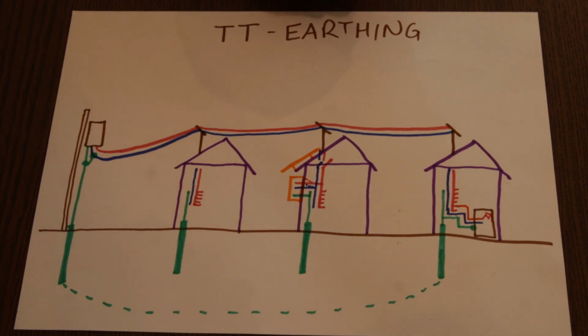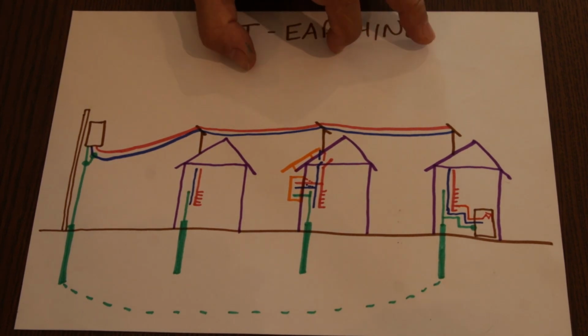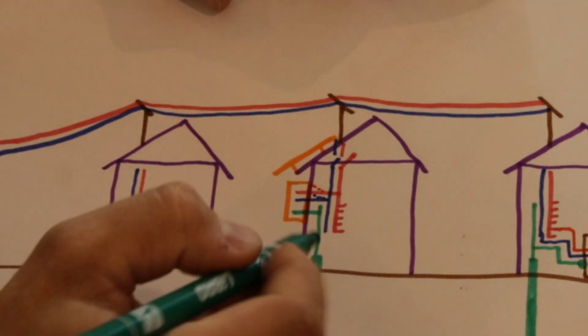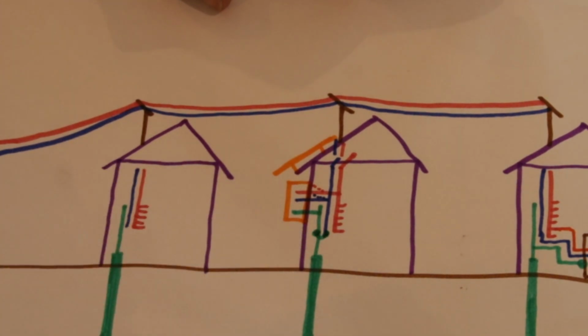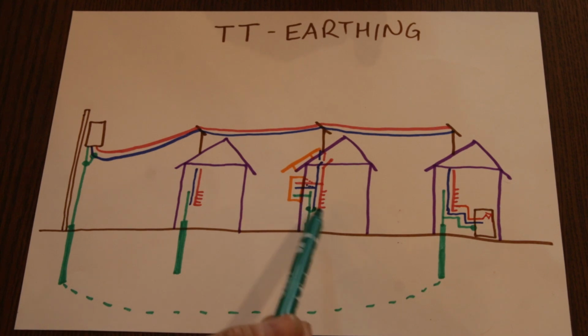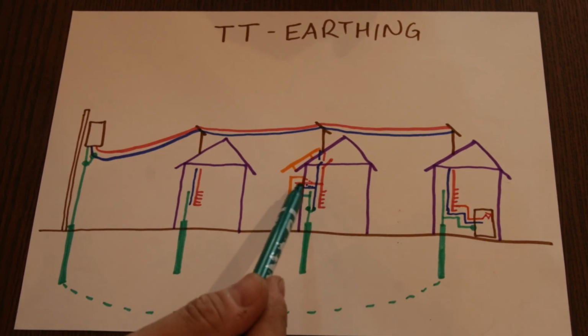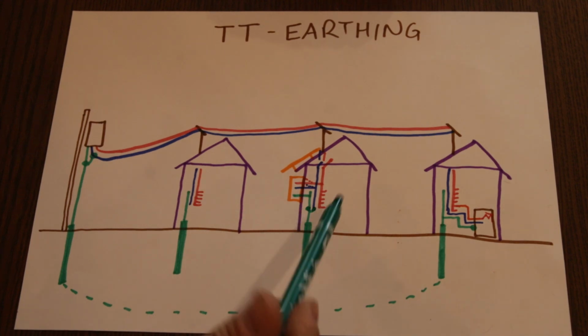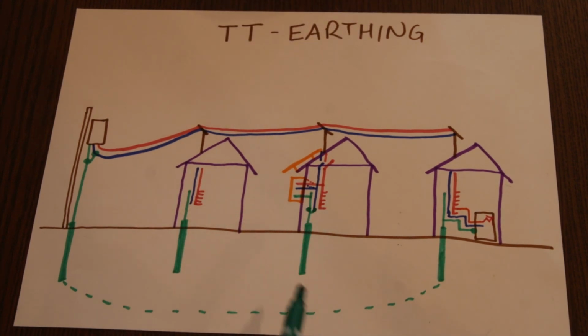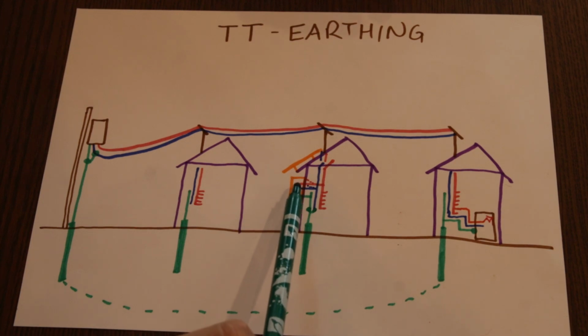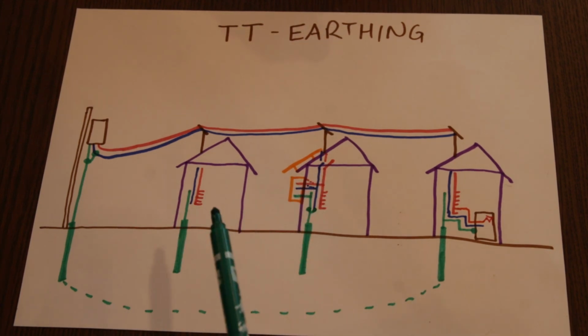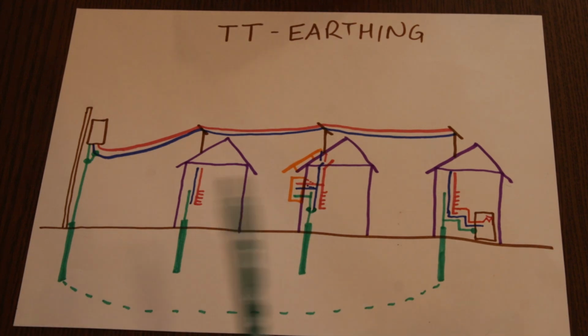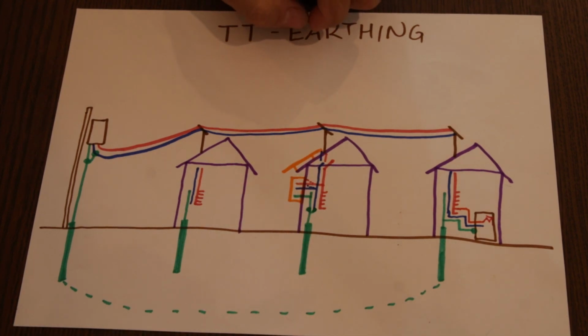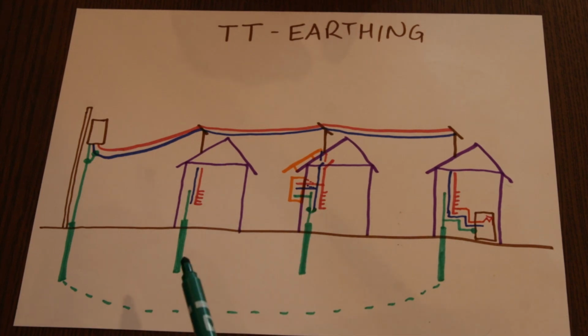So now imagine someone is putting a bond into his distribution here between neutral and ground, just to provide the inverter with grounding information, so it now knows, okay, this output wire is my neutral and the other one is the phase. If this bond is permanent and the system is now switching back to the grid supply, we would have created a neutral to ground bond for the grid as well.